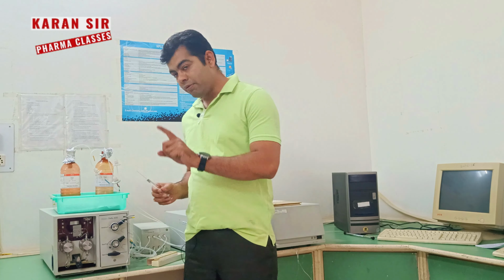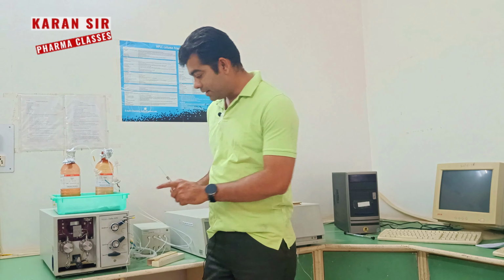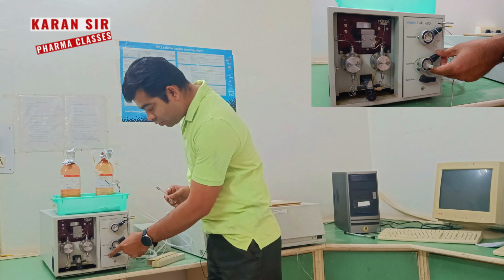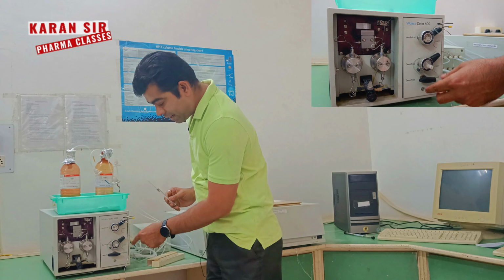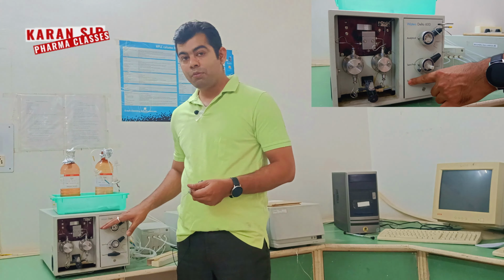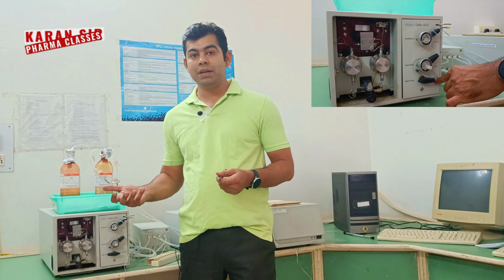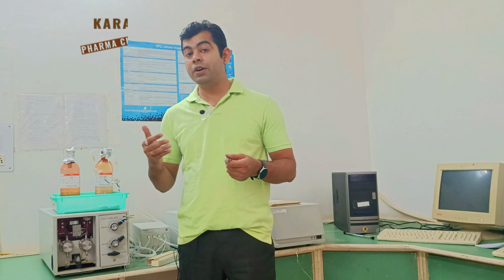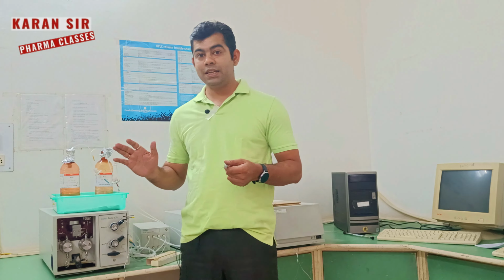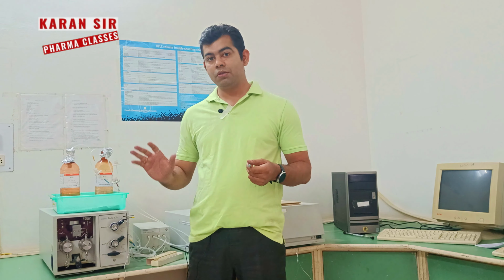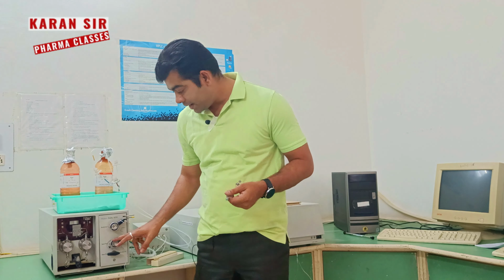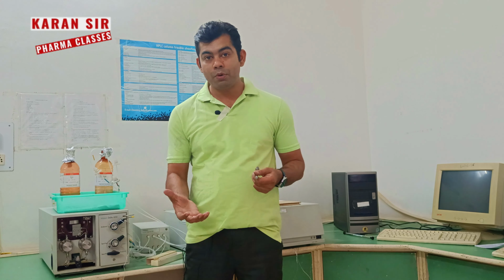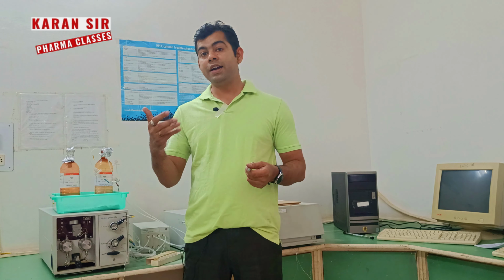One of the most important things also is that there are two modes, semi-preparative mode or analytical mode. Analytical mode is used for analysis purposes. Basically, in analytical mode we do not regenerate our sample. These are the basic uses in a quality control laboratory. But semi-preparative mode is used in R&D laboratories where we regenerate our sample.